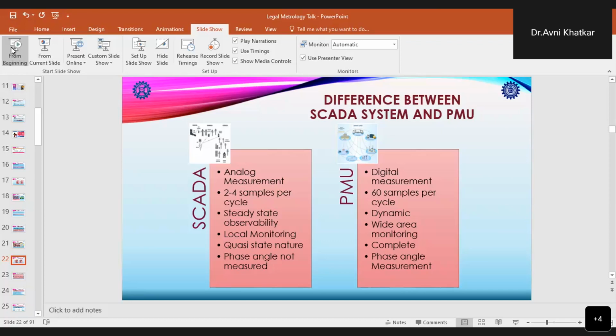So when we use a normal 104 RTU in the SCADA system, it will send readings every few seconds, and it can be used to read the voltage, current, frequency, breaker status, etc. in a substation. However, due to its very quasi-static nature, it cannot be used to read or compare phases, that is the phase shifts in the grid. So a SCADA system which is built on this cannot be used to reliably monitor the health of the grid and to isolate the trouble spots of the grid.